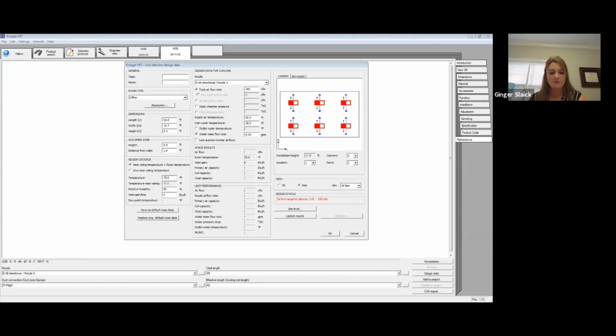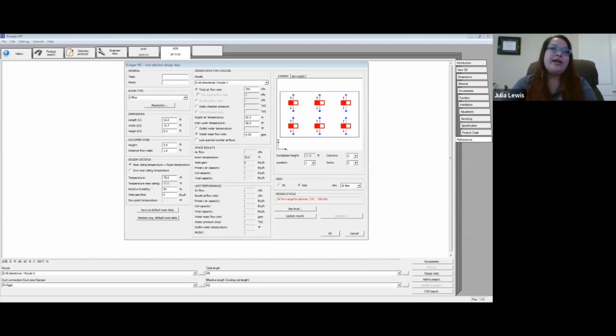Okay, thank you. We have a couple more questions, if that's okay. We'll just keep answering. During the initial startup, how should the humidity of the space be dealt with to keep them from raining? Okay, so that all depends on your dew point and where you are and how the conditions are. So if your dew point is too high, then the only way to really reduce the chance of it raining or dripping is to increase your supply air temperature, sorry. If you reduce it too much, it's more likely to drip, so you have to find that point where your environment can handle your supply air temperature without causing the dripping. So you would need to increase your supply air temperature.